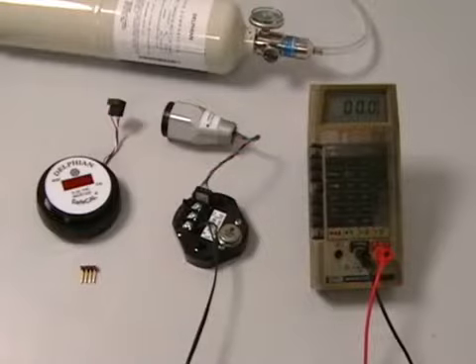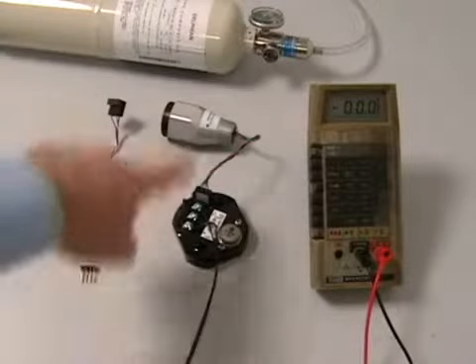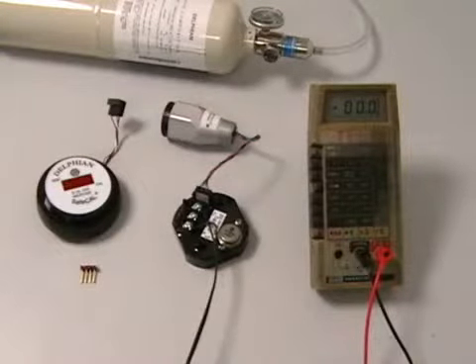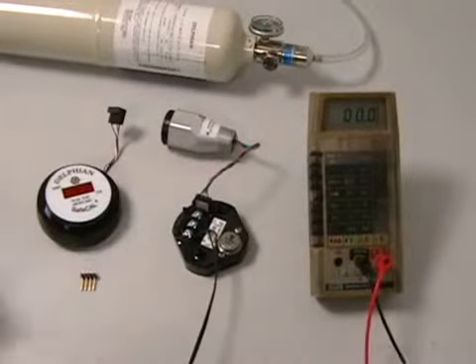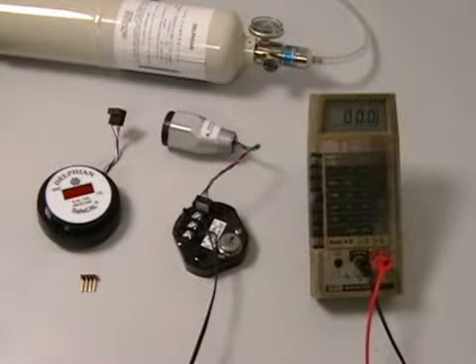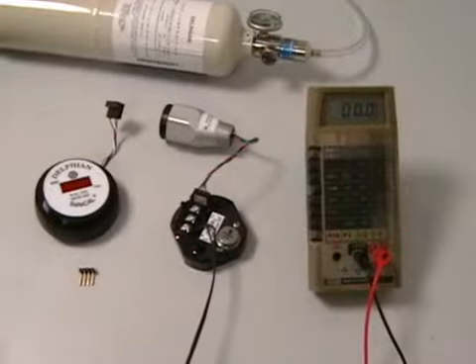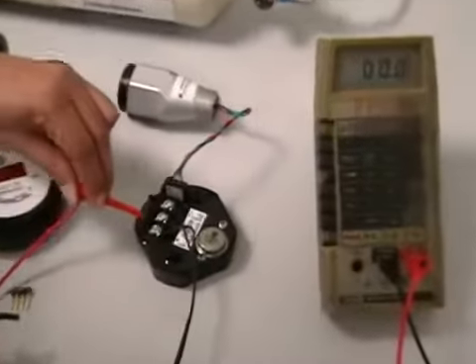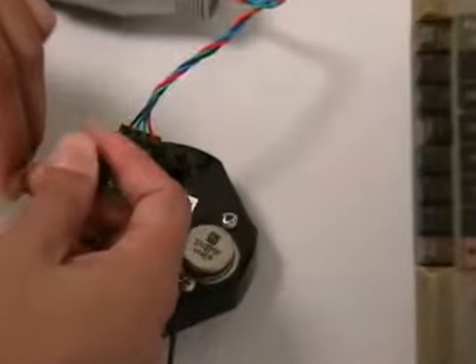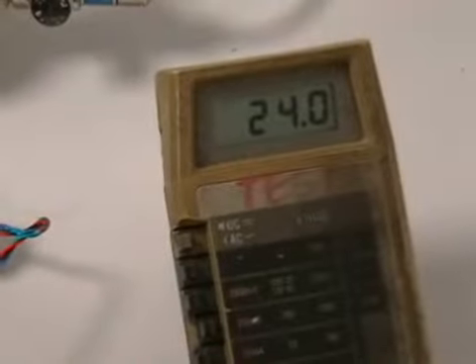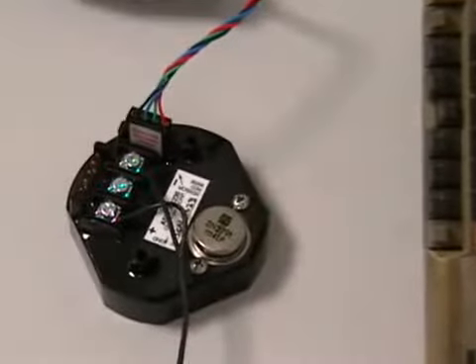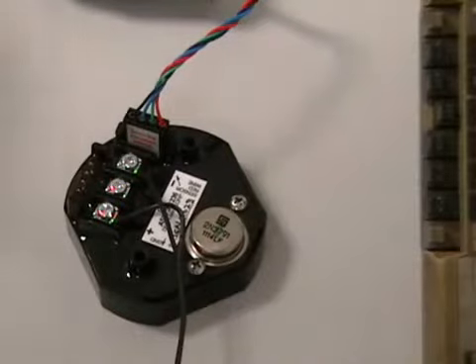There are three components in a 550 catalytic bead sensor and SafeCAL system that can be troubleshot: the SafeCAL and the transmitter and sensor. You can use any standard DVM capable of reading ohms, milliamps, and voltage. With the DVM on volts, place the probes on the plus and minus terminals of the transmitter. Although we spec out a 24 volt DC power supply, voltages from 20 to 28 volts DC are acceptable.